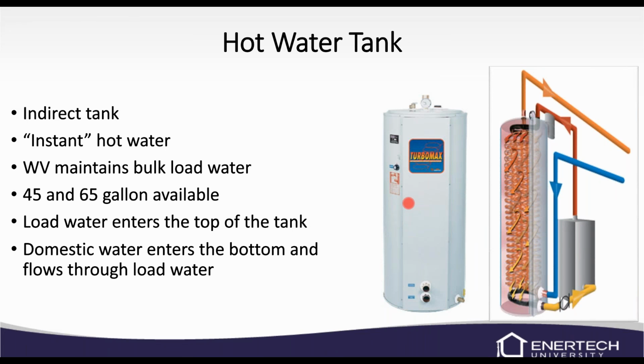Again, we discussed this hot water tank earlier. You've got a copper coil that runs through, and the domestic hot water enters the tank on the bottom, slowly picks up heat as it rises through the bulk load water, and then goes out to your home. The WV unit pumps the hottest water into the top, and it circulates through the bottom and comes out the bottom and returns to the unit. That's that reverse return. When our water temperatures are closer together, we transfer heat better. So in this reverse return, the hottest water from the WV unit will be in contact with the hottest water in the domestic hot water circuit.